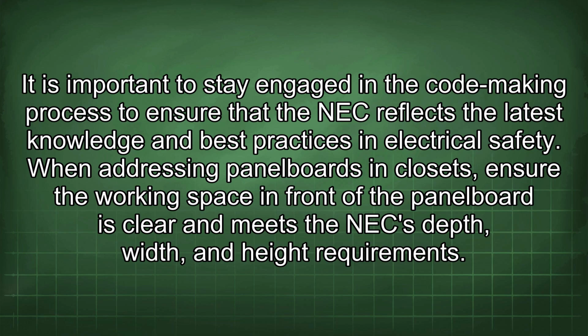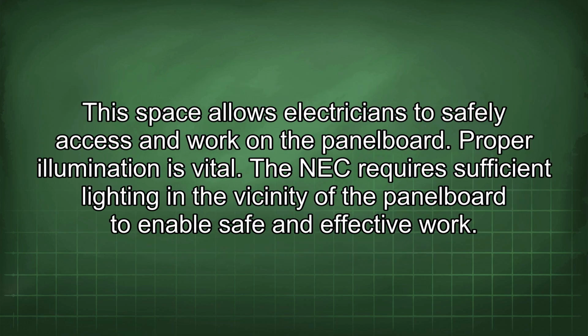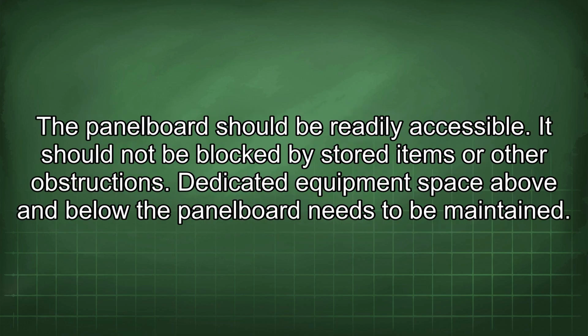When addressing panel boards in closets, ensure the working space in front of the panel board is clear and meets the NEC depth, width, and height requirements. This space allows electricians to safely access and work on the panel board. Proper illumination is vital. The NEC requires sufficient lighting in the vicinity of the panel board to enable safe and effective work. The panel board should be readily accessible.